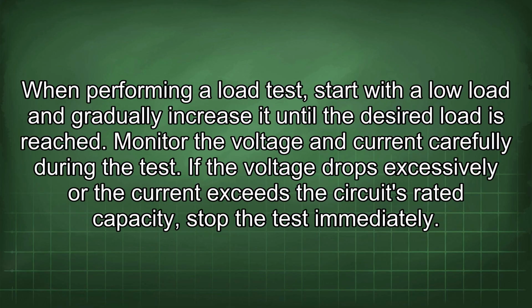When performing a load test, start with a low load and gradually increase it until the desired load is reached. Monitor the voltage and current carefully during the test. If the voltage drops excessively or the current exceeds the circuit's rated capacity, stop the test immediately.